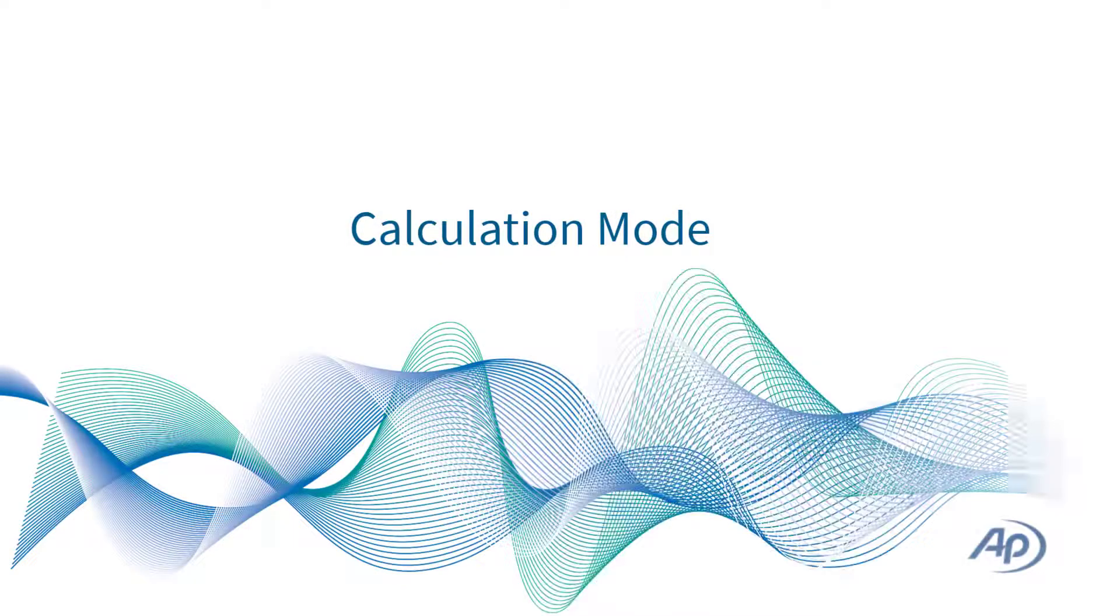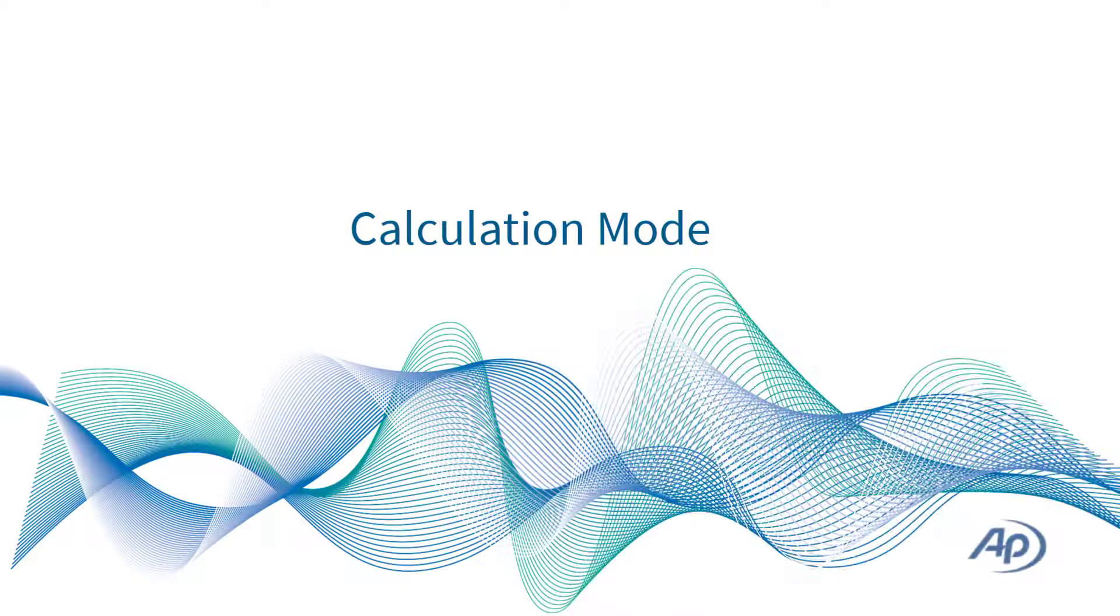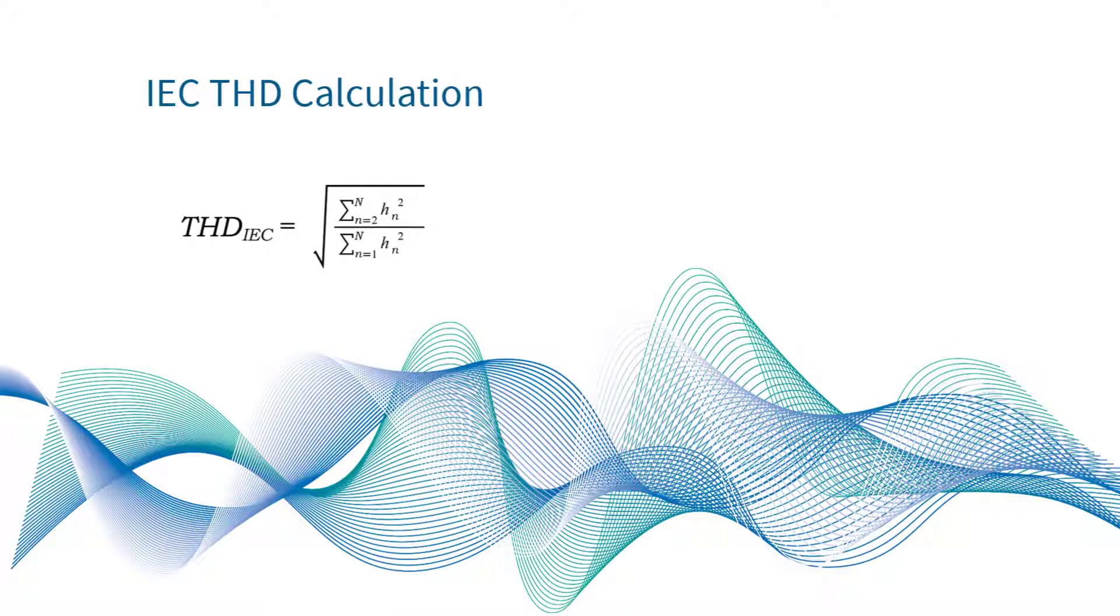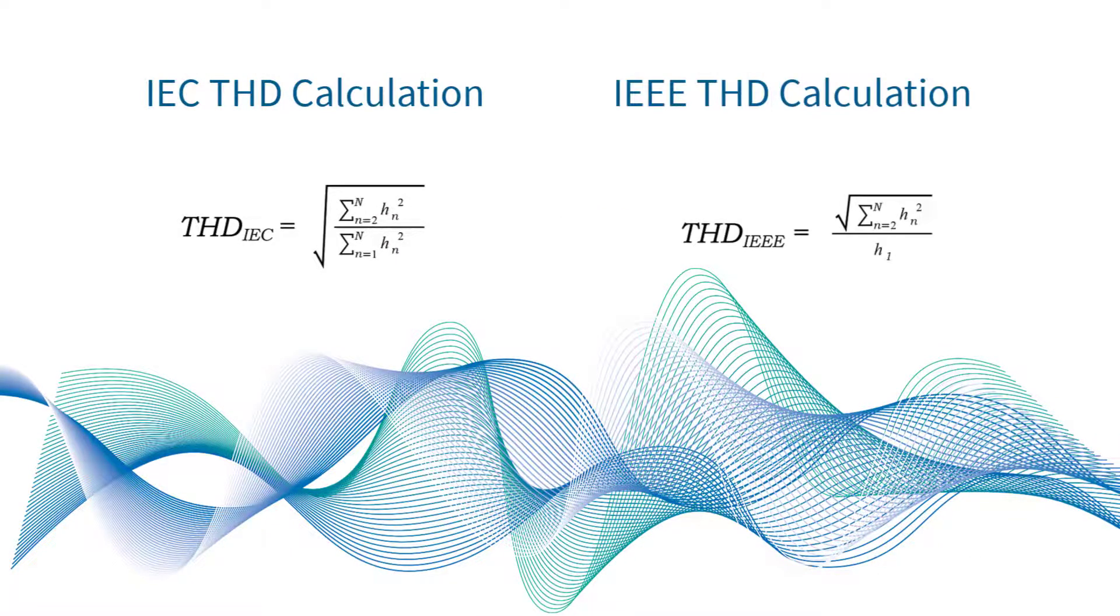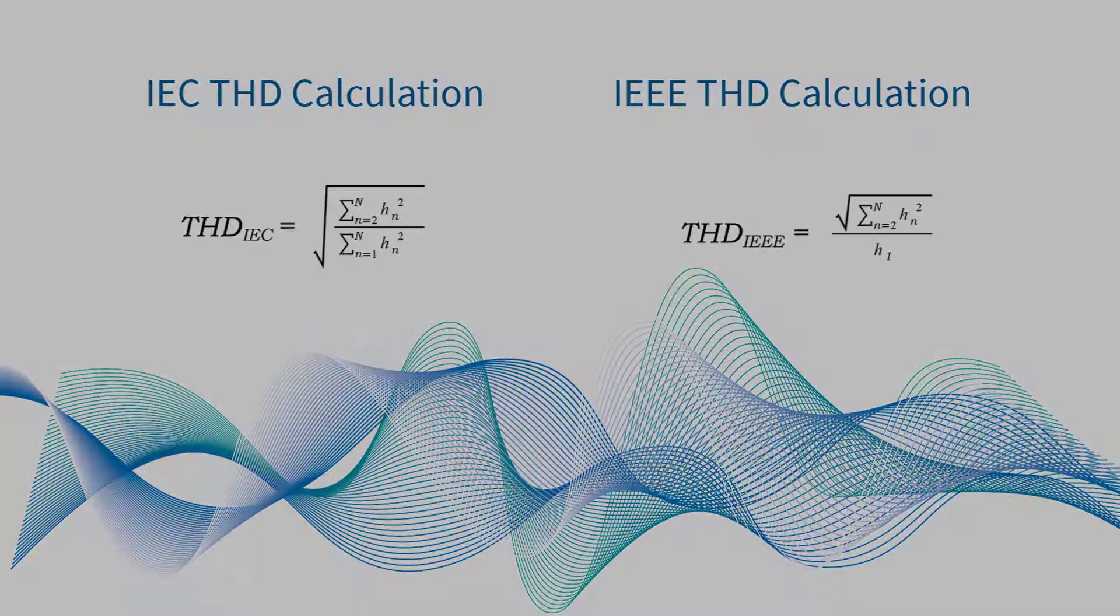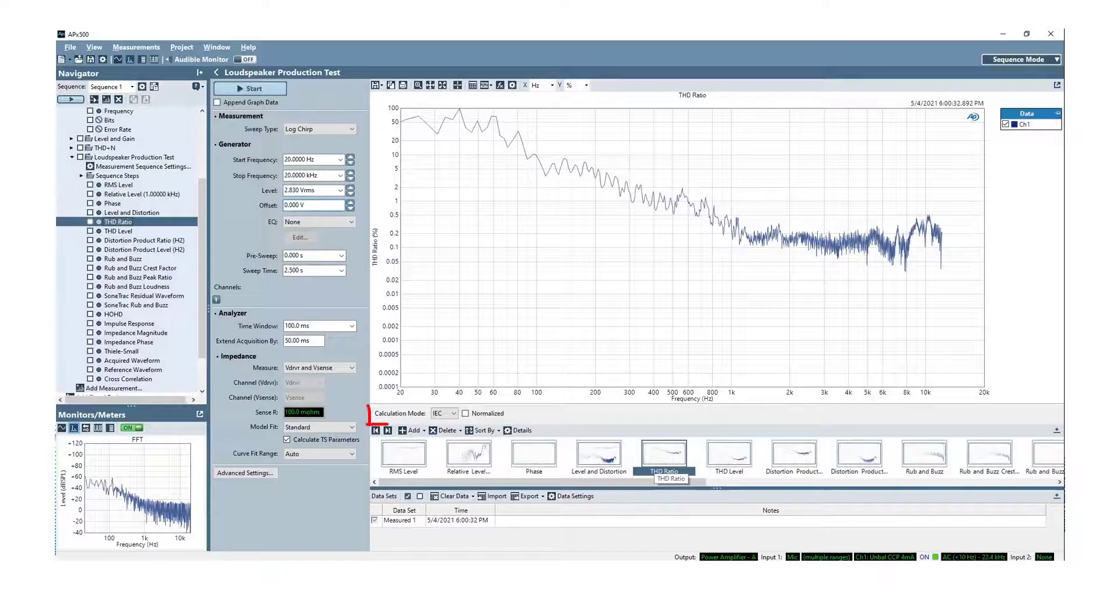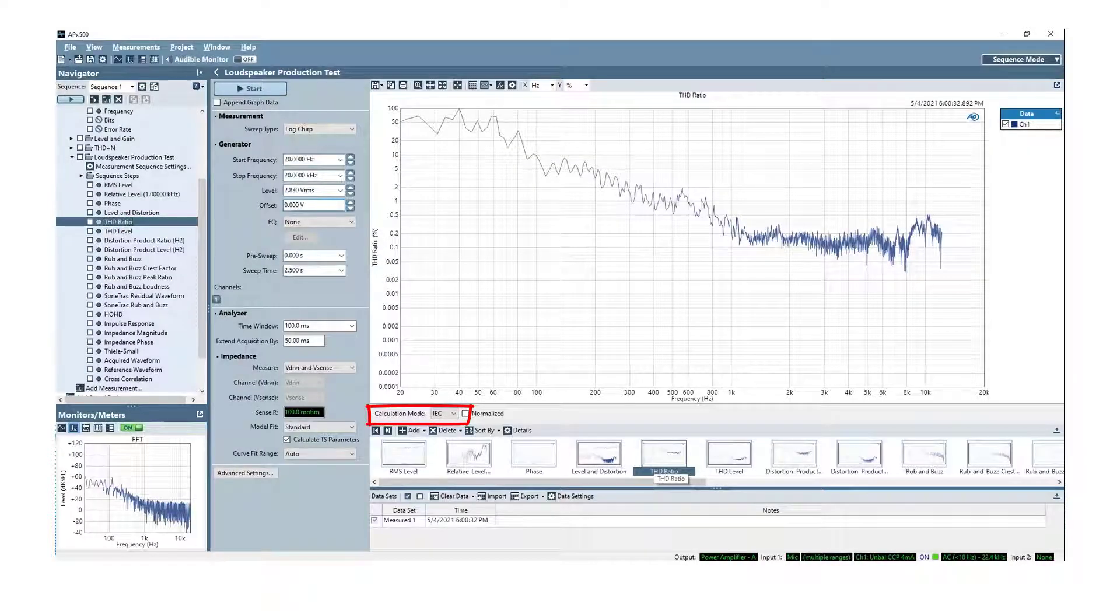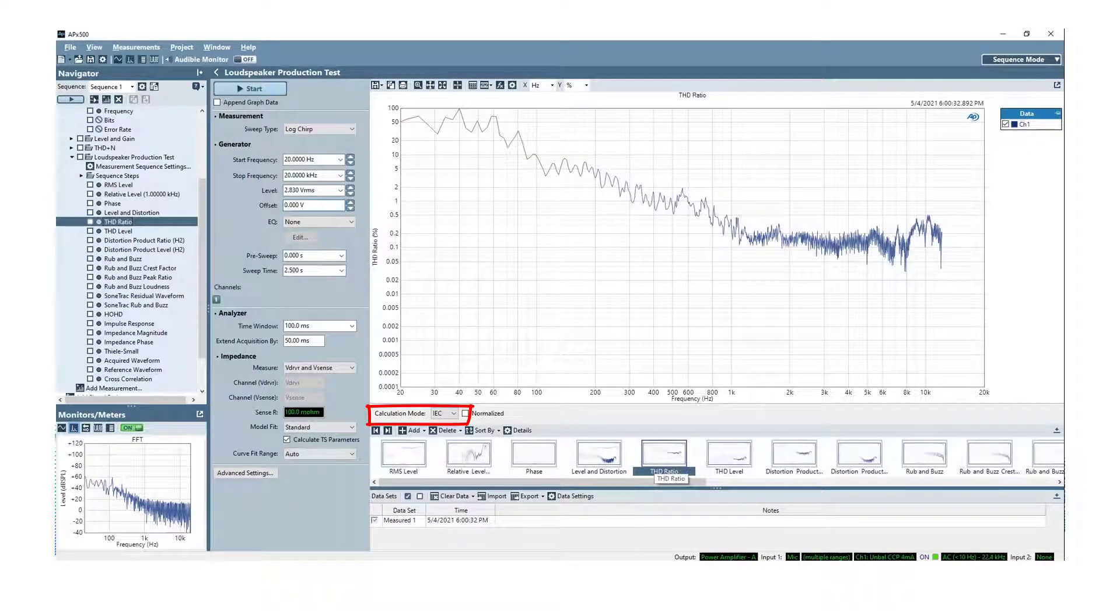Let's take a closer look at each control. IEC and IEEE standards use slightly different methods for calculating harmonic distortion when analyzing the response of a device under test. The Calculation Mode parameter allows you to quickly display THD results according to each standard.